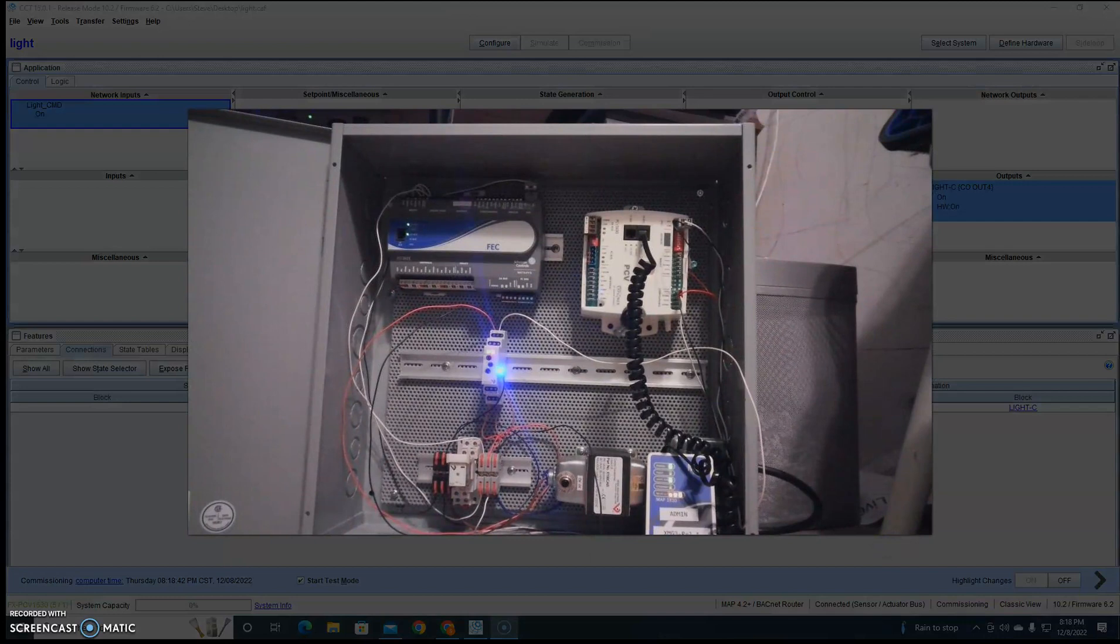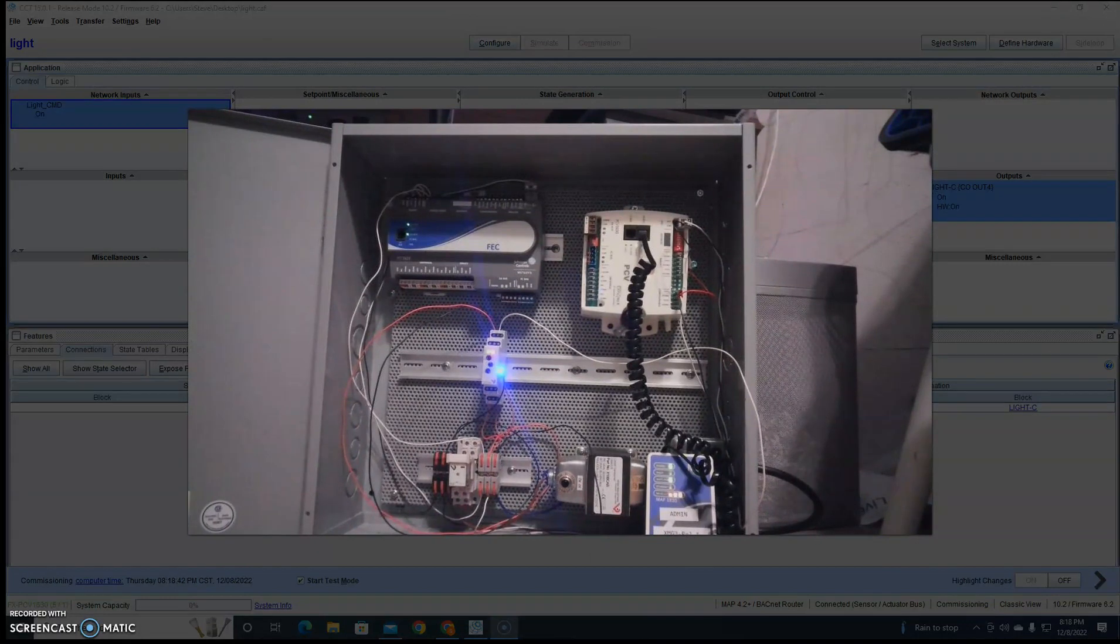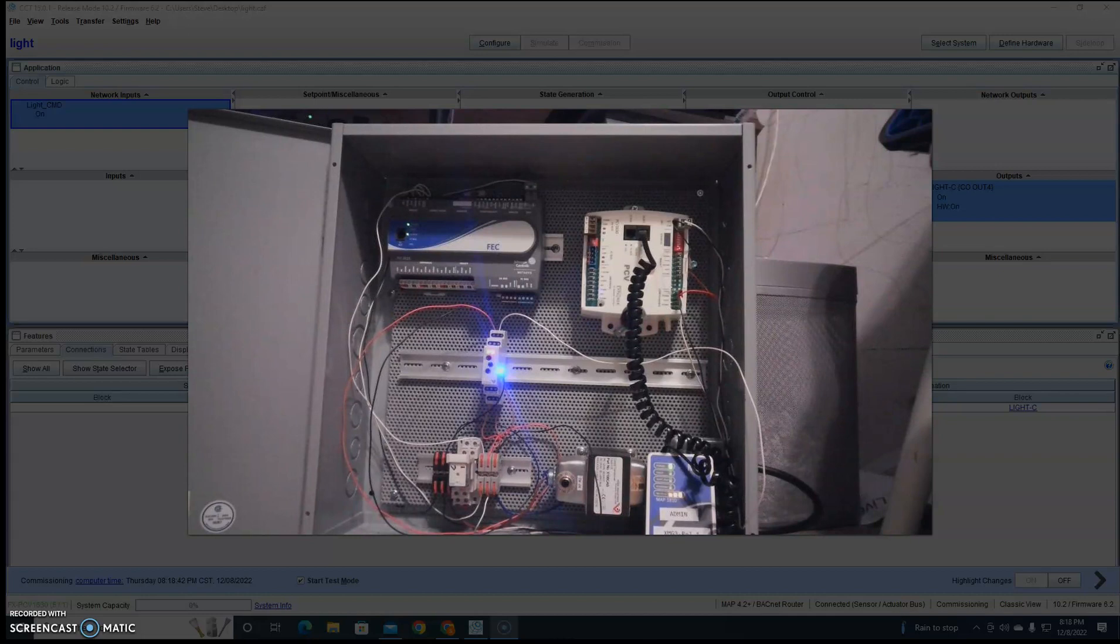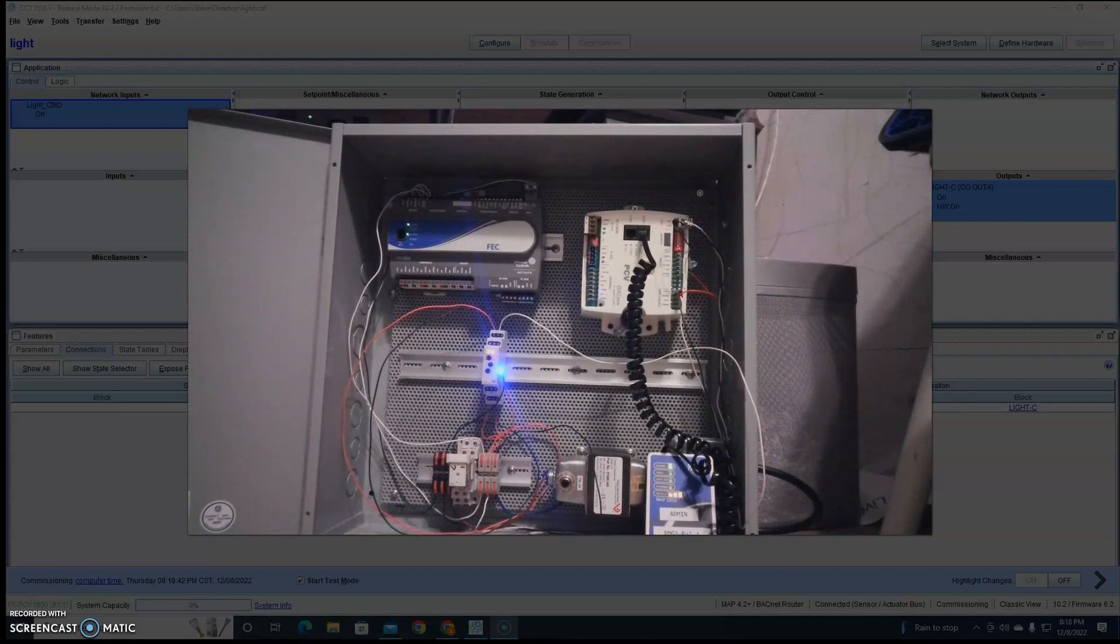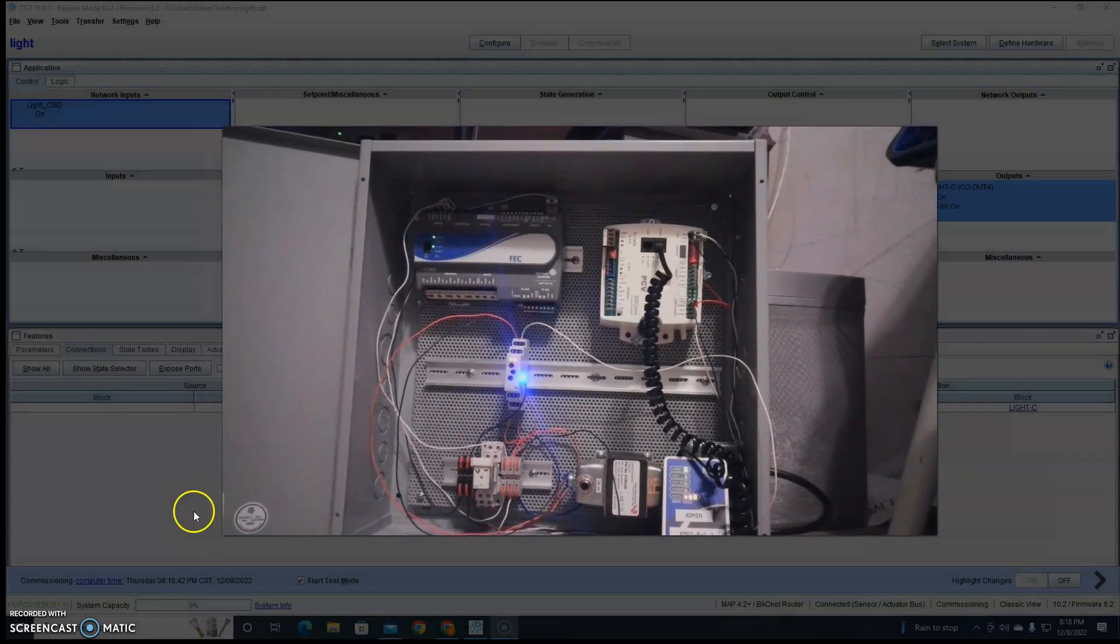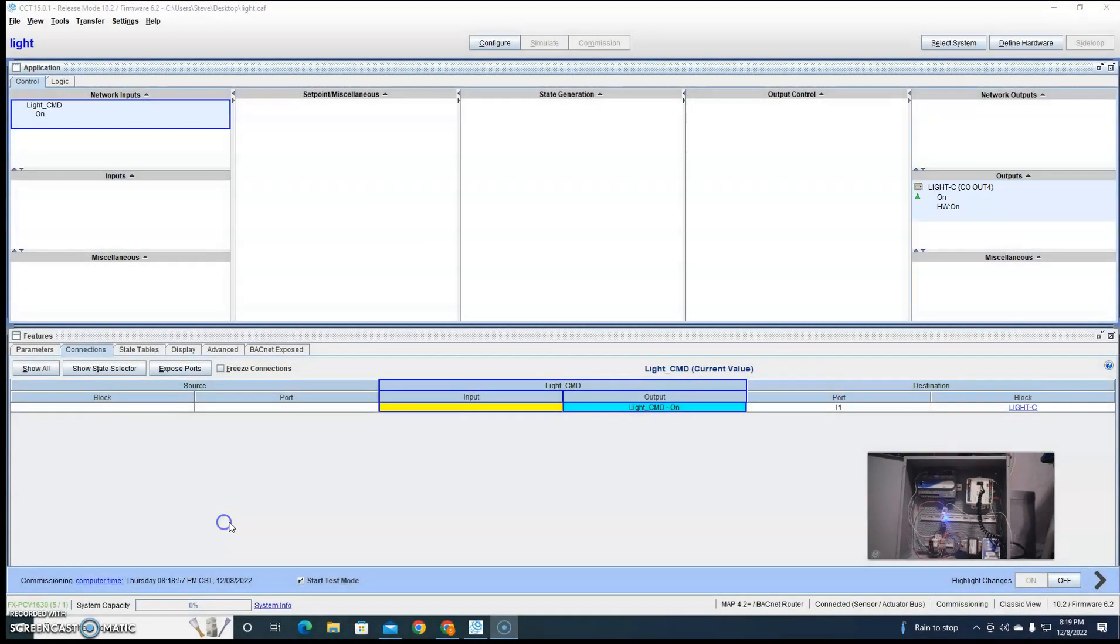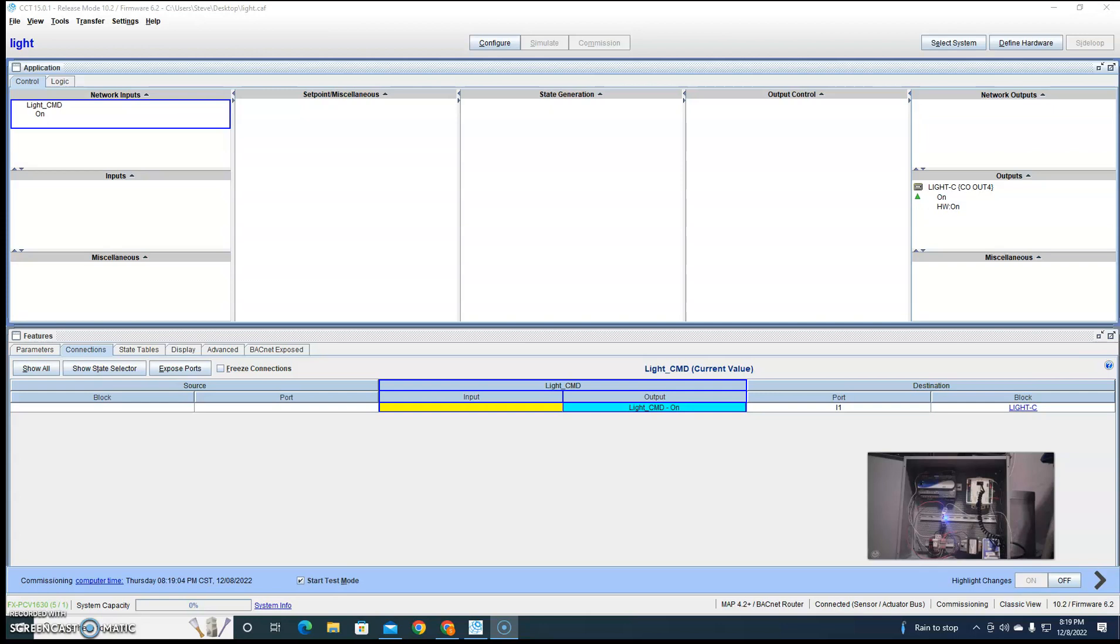So the green light came on for a second and went away, and now the blue light's on, right? So the relay is latched right now, even though the output still says on. The controller is no longer outputting a signal anymore. So it's an open contact at this point.